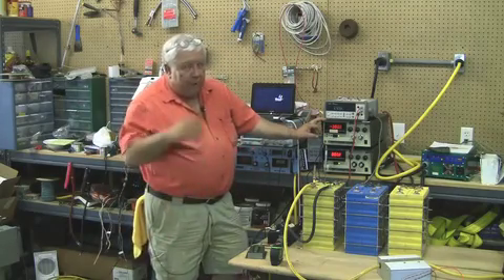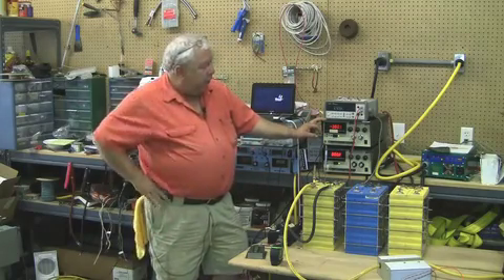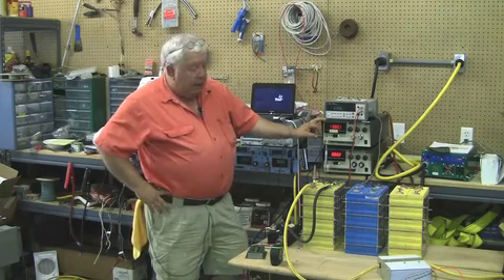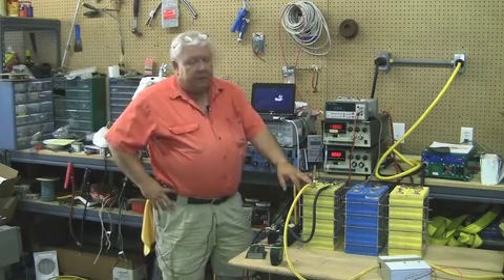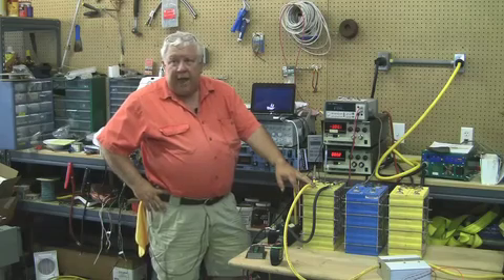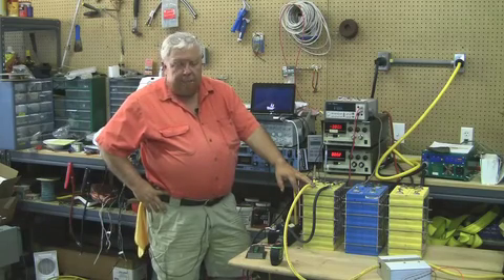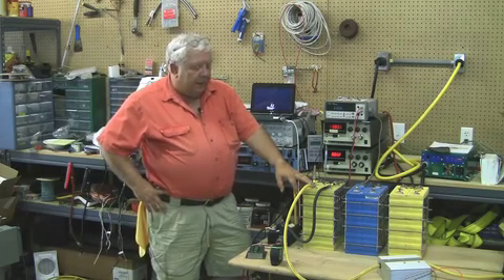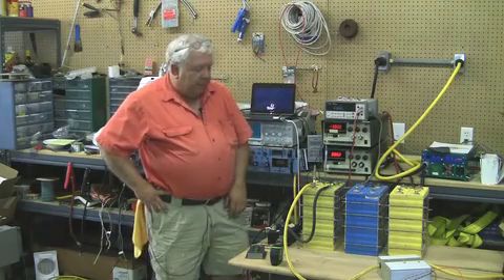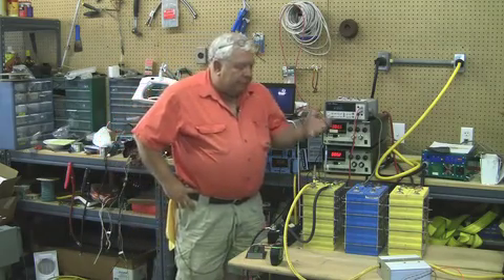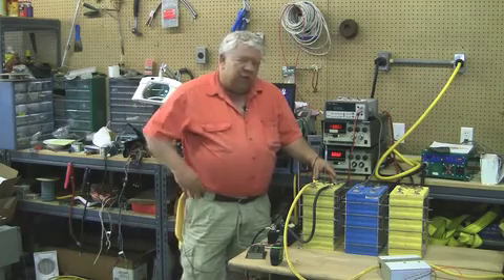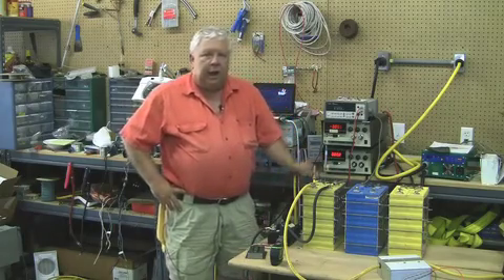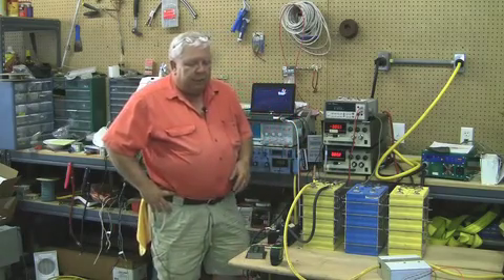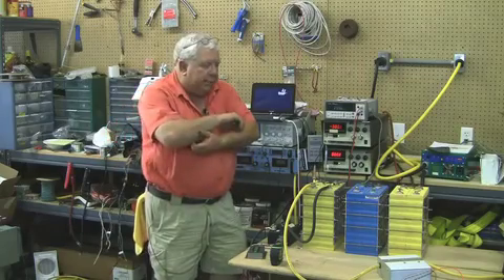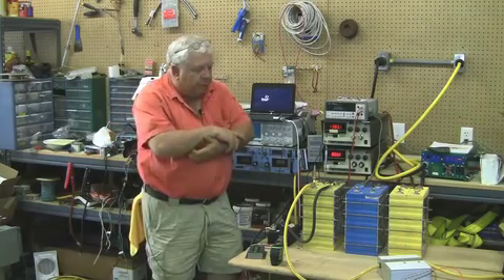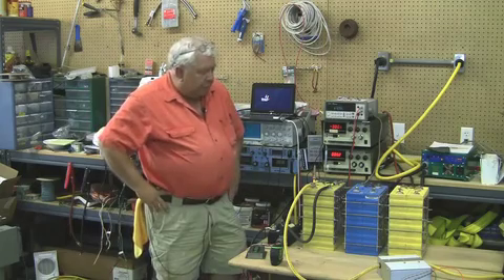Probably next week, I'll show you how to do some 3C testing. We're actually going to do some pulse testing, simulating a drive at 3 times the rated capacity. In this case, some 600 amps - actually, we'll use the 100 amp cells, so it's a little less. Do 100 amp cells at 3C, it'd be 300 amps; 90 amp cells would be 270, that sort of thing.